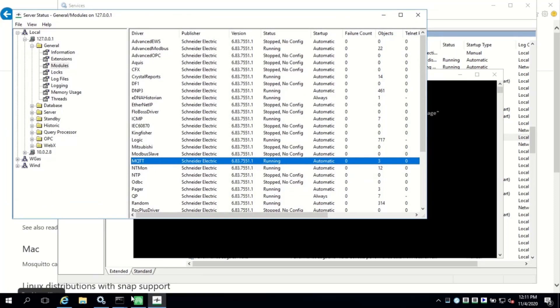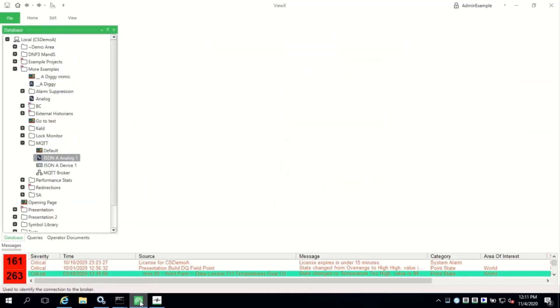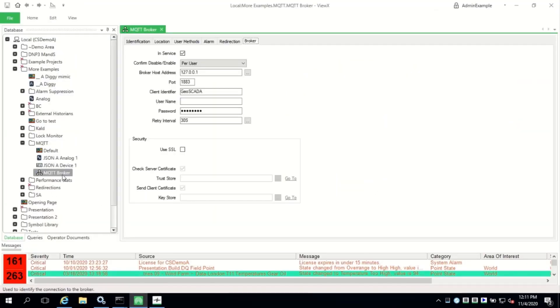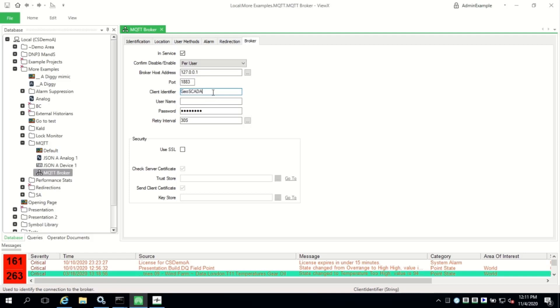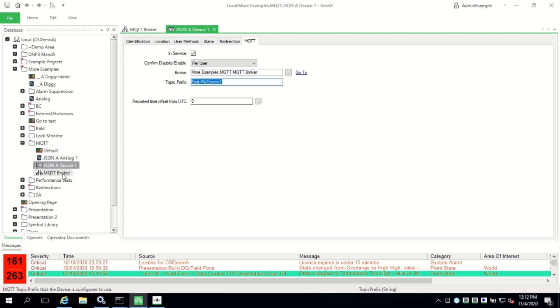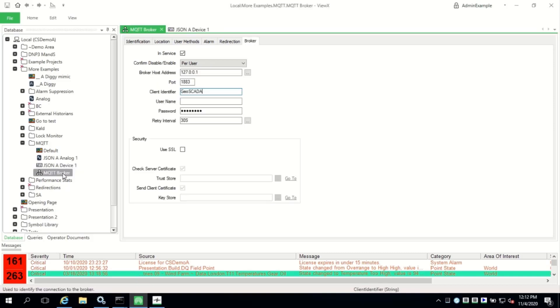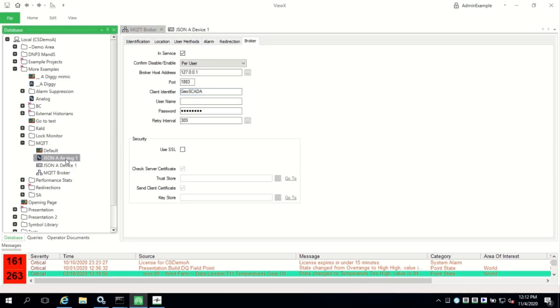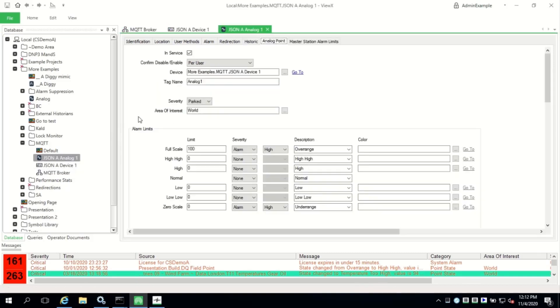Now create the GeoSCADA objects for the broker, device, and points. I've created these in advance, and the fields to note are for the broker, the host address, and the port. Note that the client identifier cannot be blank. It doesn't really matter what goes in there.